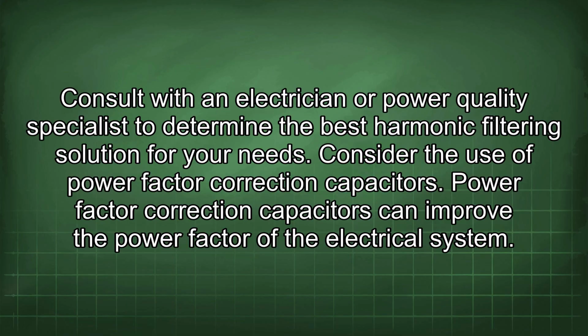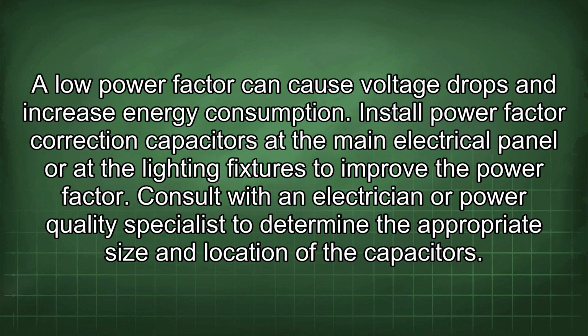Consider the use of power factor correction capacitors. Power factor correction capacitors can improve the power factor of the electrical system. A low power factor can cause voltage drops and increase energy consumption. Install power factor correction capacitors at the main electrical panel or at the lighting fixtures to improve the power factor. Consult with an electrician or power quality specialist to determine the appropriate size and location of the capacitors.